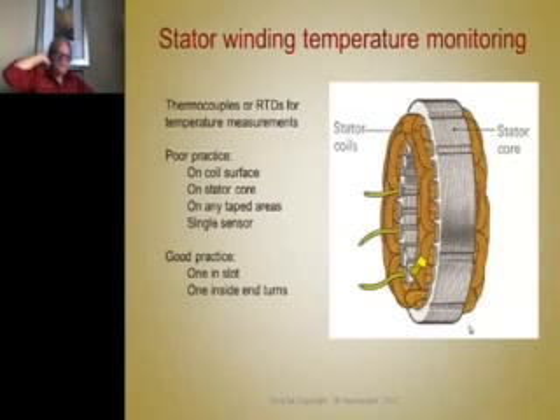So I always recommend that you monitor the temperature of stators. If you use thermocouples, I prefer RTDs, but use thermocouples or RTDs and mount those inside the stator so that you can measure the temperature for R&D purposes, or measure the temperature to tie that in with control, inverter control, so you cut back on the current before you fry the windings. This is a very good practice with the modern inverters. Some standard inverters you buy have this input.